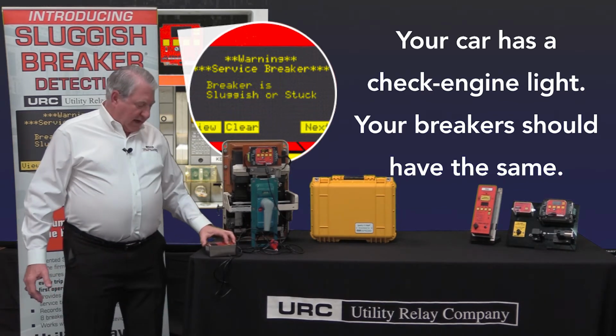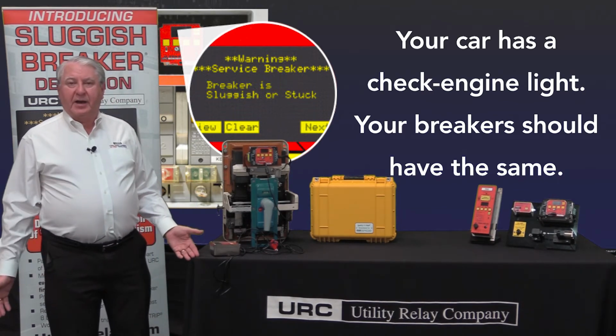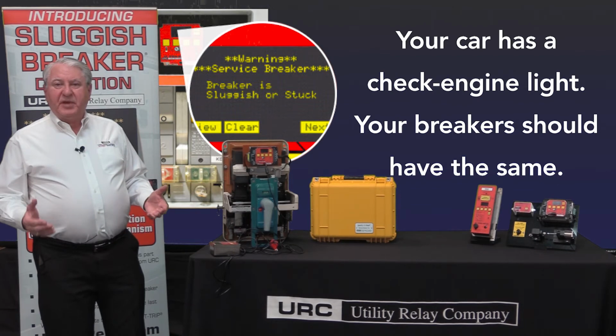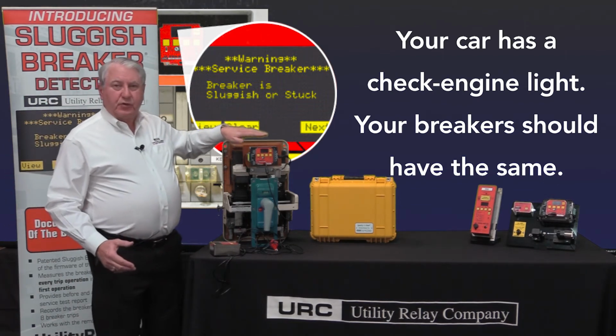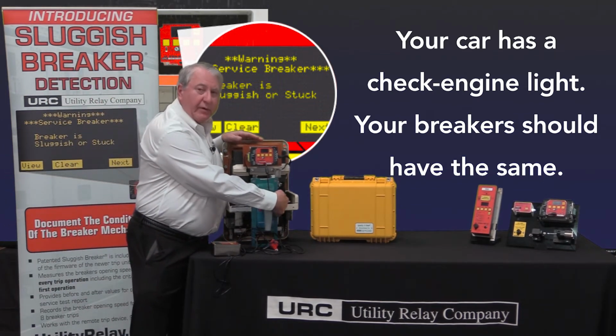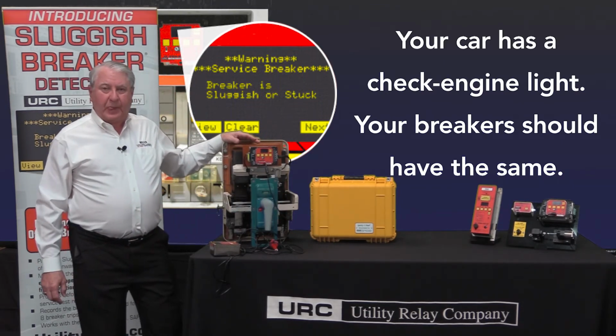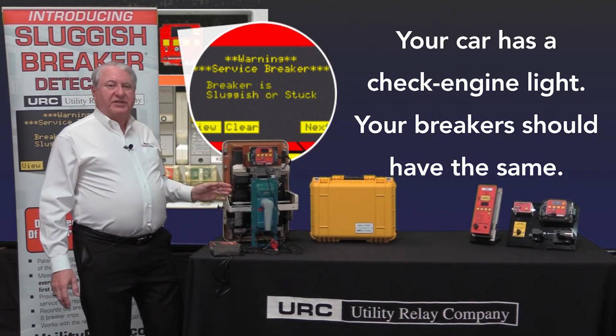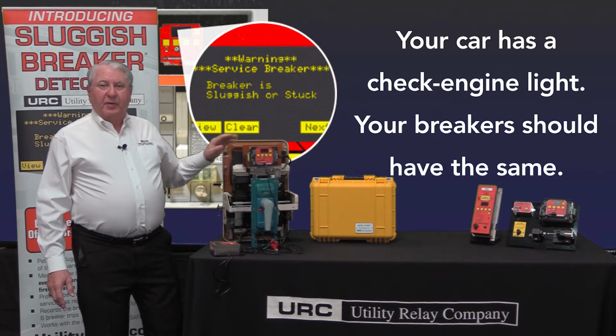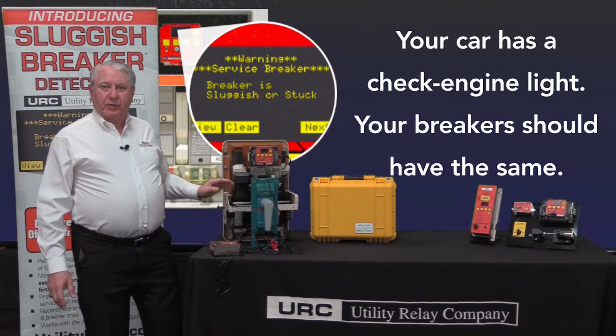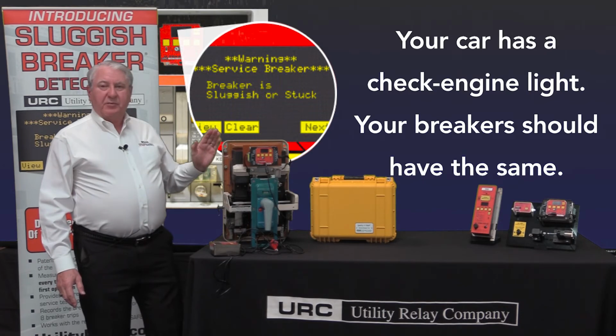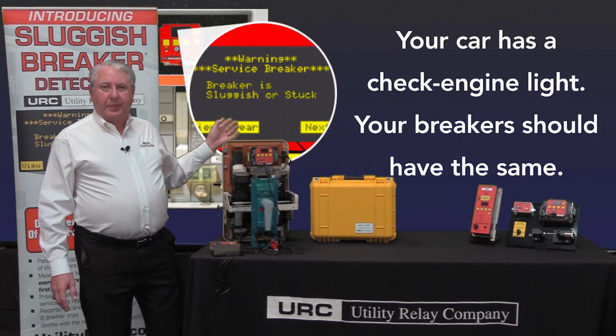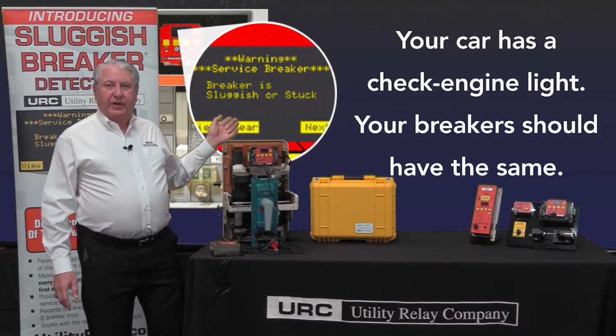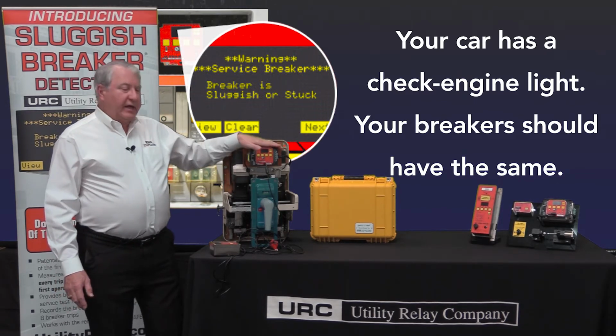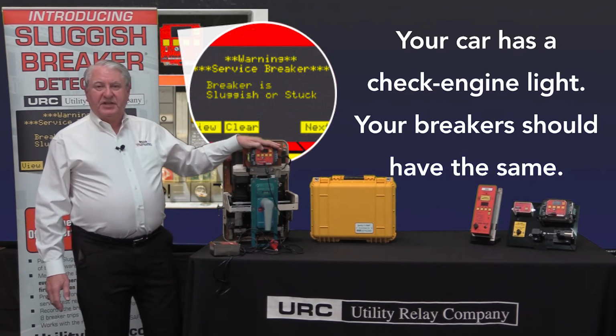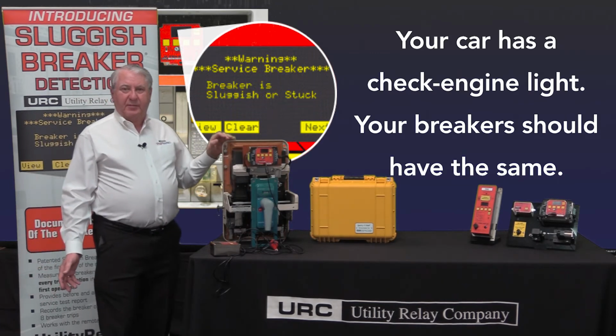So how does that work? How do we accomplish that? Well, the timing is done when the trip unit sends an impulse to the actuator to start the tripping operation, and it stops when an impulse comes back to the trip unit from a micro switch that's part of our retrofit kit. When that micro switch changes state, when it's hit by the breaker operation and changes state, it sends a message back to the trip unit and stops that timing.